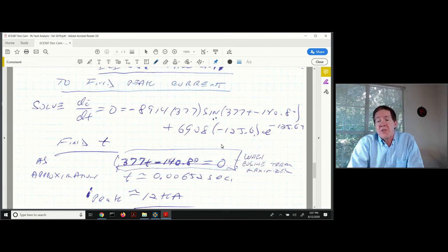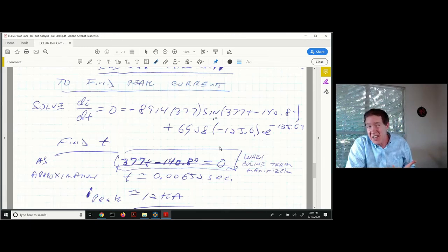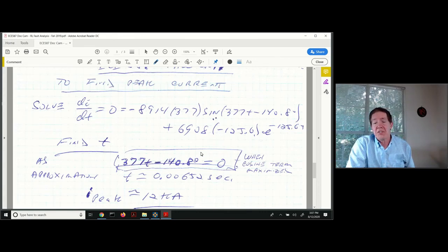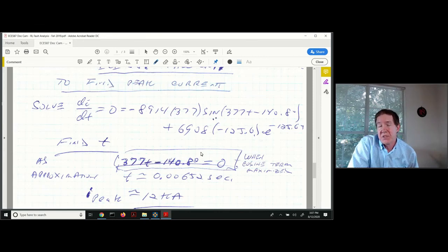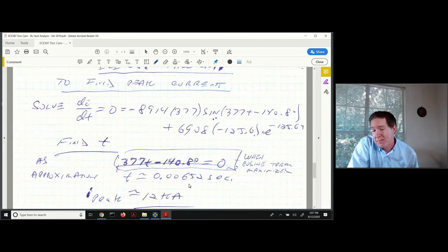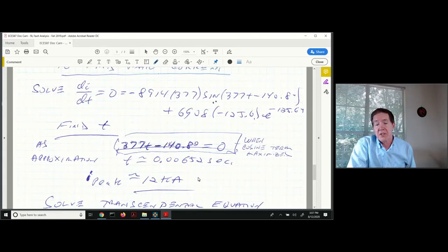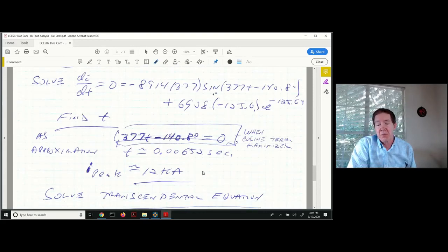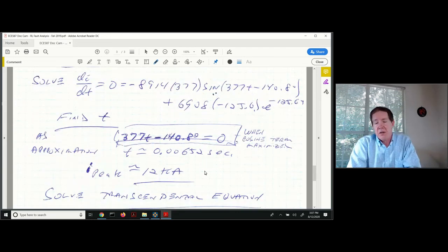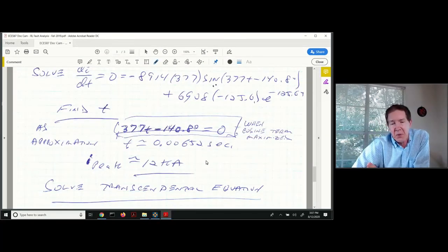You could use numerical techniques to find the time that satisfies this equality. But usually what you would do if you just want to get close is look at what does 377t minus 140.8 need to be to make cosine of that equal to 1. This just has to be 0. You solve for time. Time would be 0.00652 seconds. You can plug that back in, and you get an approximation for what this peak value is at 12 kiloamperes.